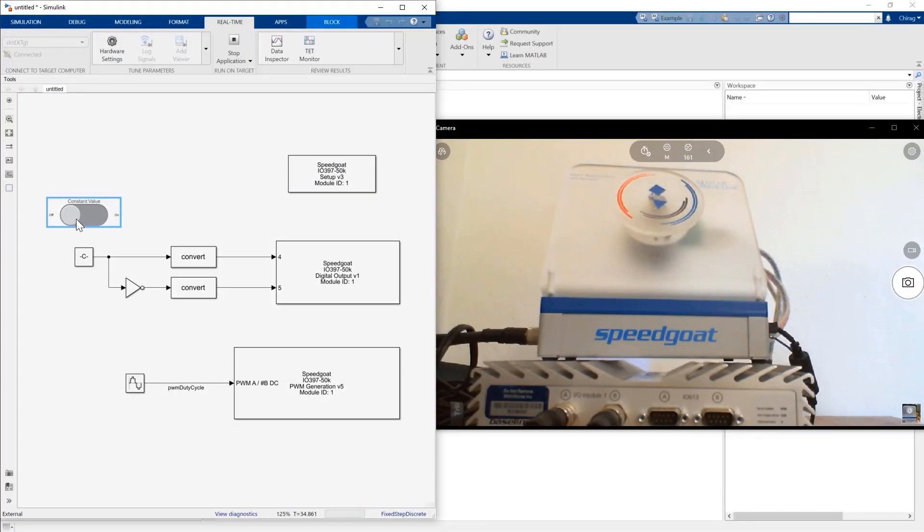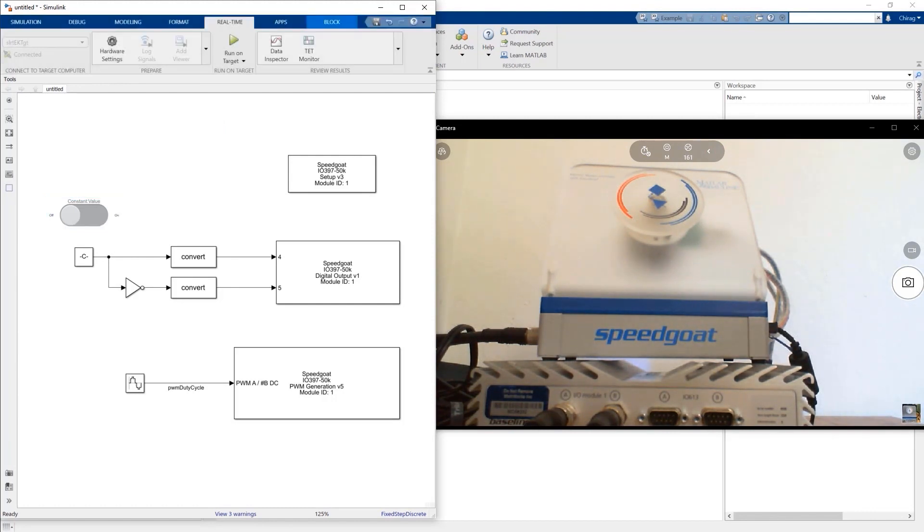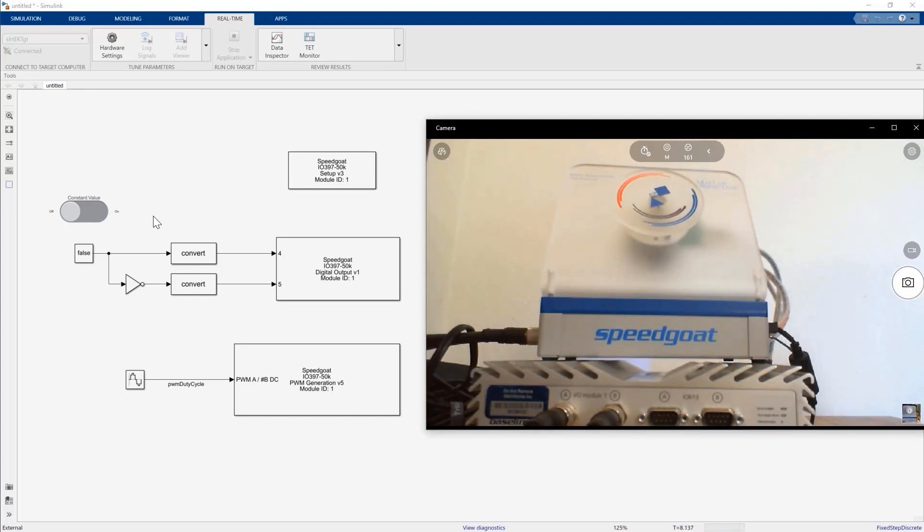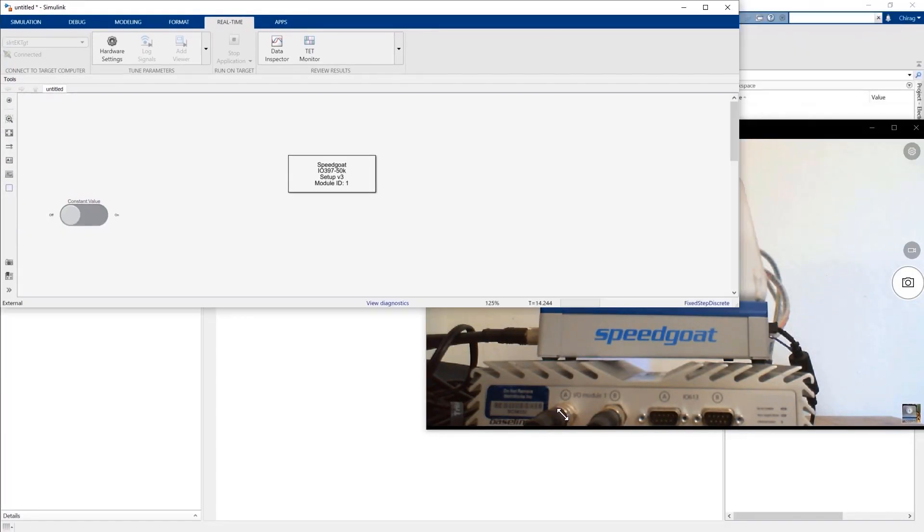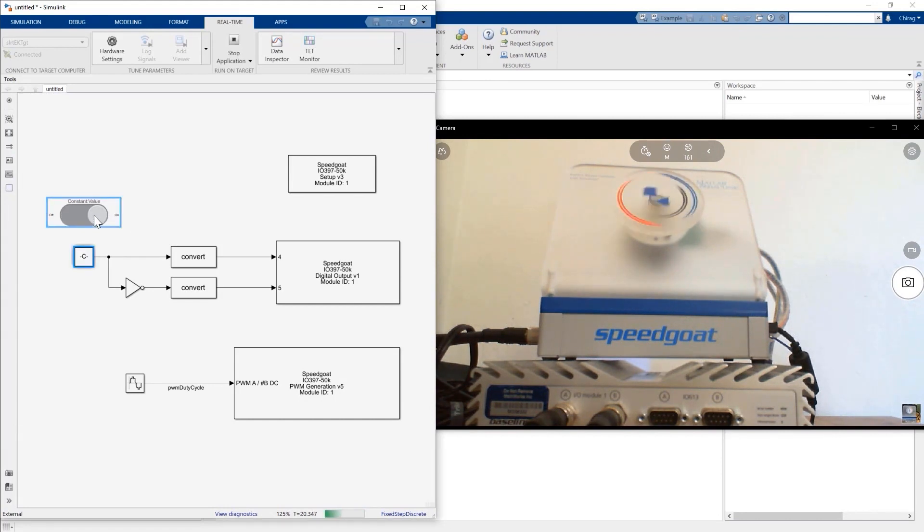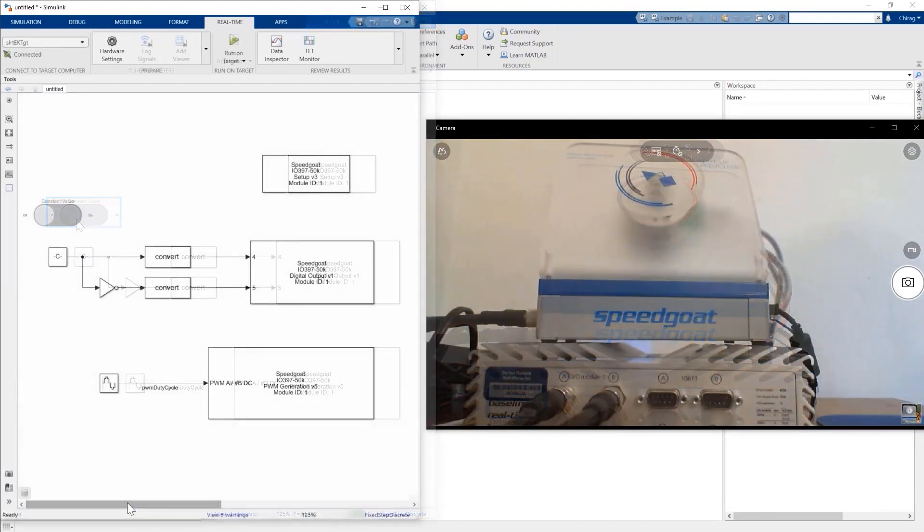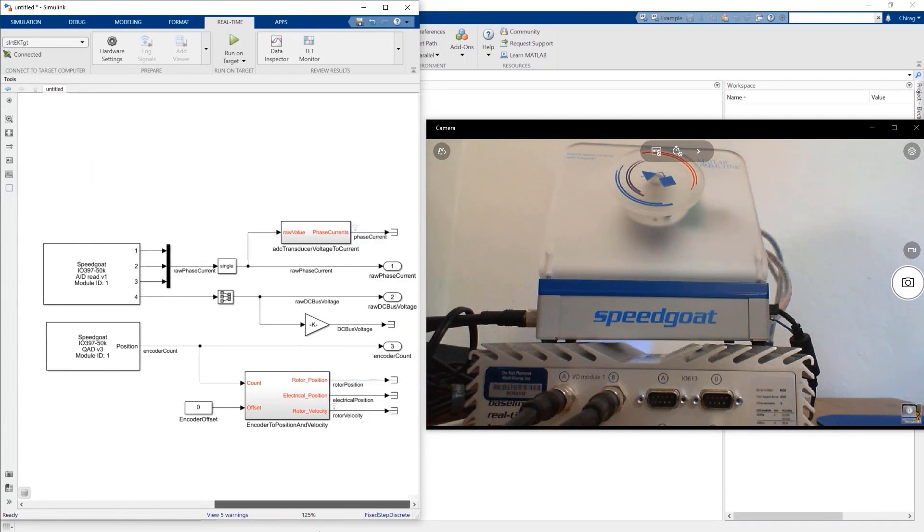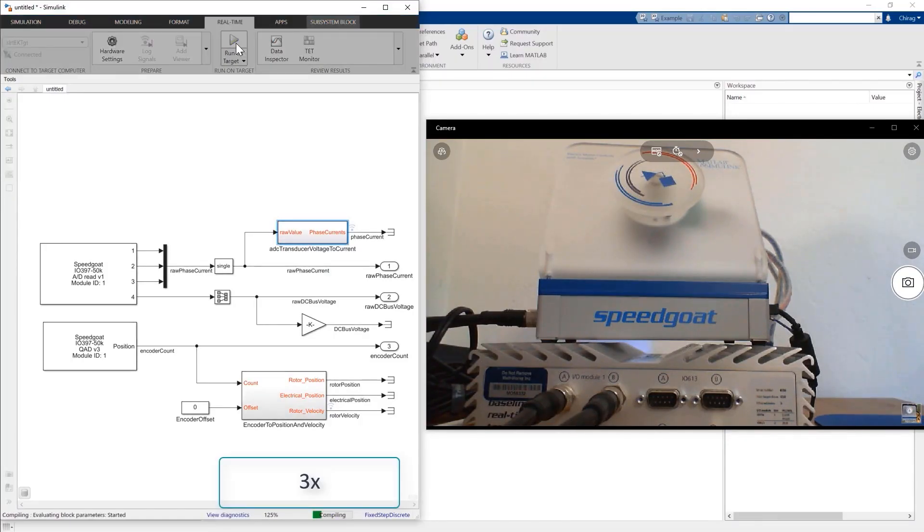The motor will start spinning. We are first just spinning the motor with scalar control. We basically provide 3 phase sinusoidal voltages whose amplitude and frequency will create a rotating magnetic field that will also start rotation of the permanent magnets in the rotor. As the motor spins, we will be measuring the rotor rotation and 3 phase currents using IO configured with SpeedGoat driver blocks. We are now commissioning our input and output interfaces with the drive and electric motor.